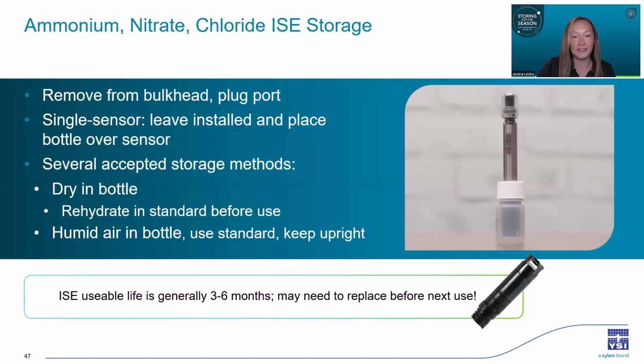Another option is to keep the ISE in humid air. So you'll put a small amount of standard in the bottle and seal it. You don't want to use tap water or DI water for storage, and you don't want to submerge the sensor tip in the solution. Keep the sensor upright so it doesn't come in contact with the solution. As you can see in the photo there, the sensor tip is kind of just hovering above that solution, not submerged in it. That's great. That's kind of what you want to see.